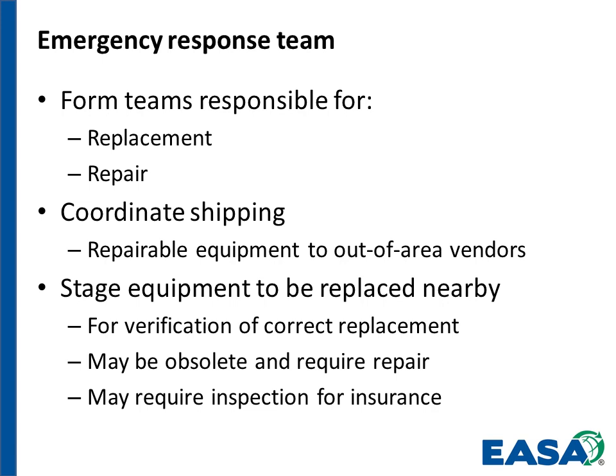So it's important that the stuff we're going to replace, the electric motors, the switchgear, and so on, be staged in some area that's convenient but well out of the way, so it's not an obstacle to all the repairs that are going to be going on. And that may be a large parking lot area or someplace where we can stage things so that if we discover that something's not available to replace in a reasonable time, we can pull that out and move that to the repair side of the equation.